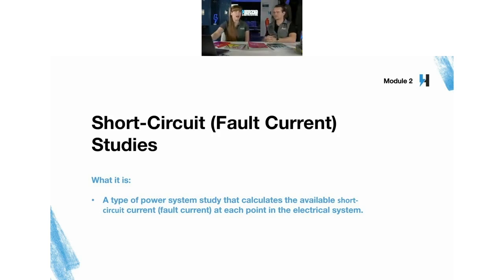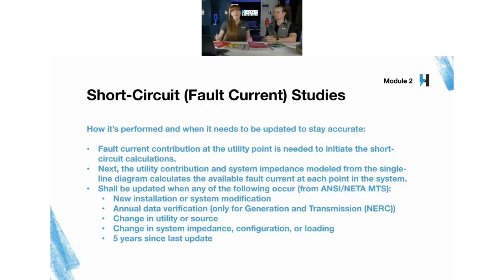All right, so how do we do that? We've got our one line diagram, right? Well, first you'll need some kind of source to initiate the study. Typically, it's a utility contribution from data that you get directly by contacting the utility. They'll provide you the fault current information at the utility point that you saw at the top of the one line diagram in the previous slide. And if you run generators, maybe that as well. Yeah, for sure. And then also the single line diagram itself is needed, which is the modeling of the impedance of the equipment. You'll need that for the calculation as well.